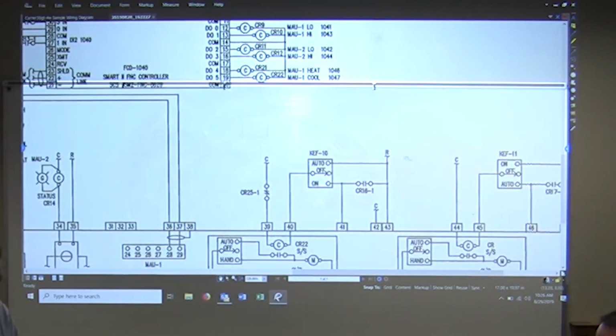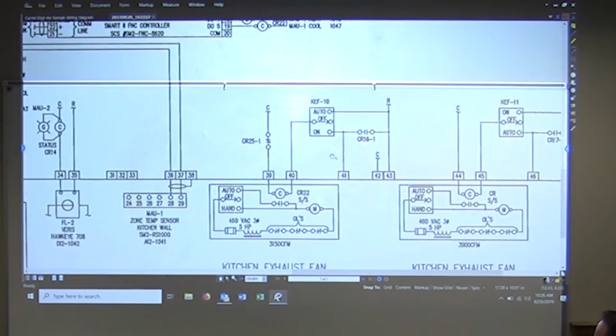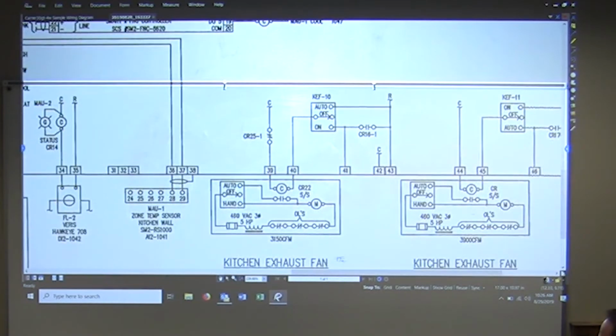So here is an example of what we normally don't do. CR25 is not on your drawing. It's on this maybe page 2 or something. But what is the effect of CR25 on this part of the circuit? So this is the kitchen exhaust fan, number 10. So what is this relay going to do? Let's energize it. So if it opens, what does that do to the fan?